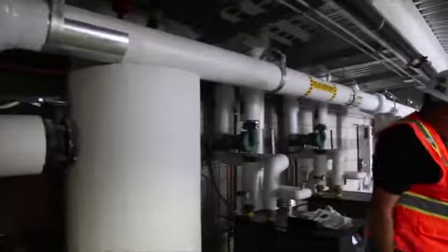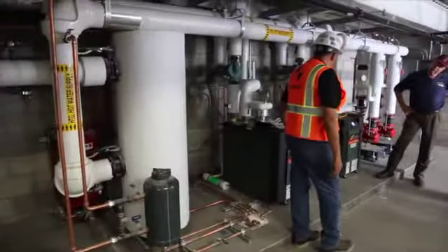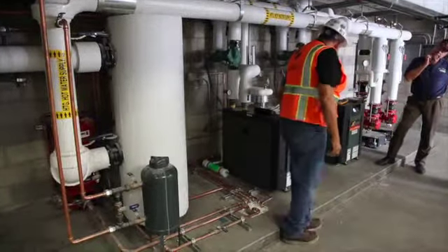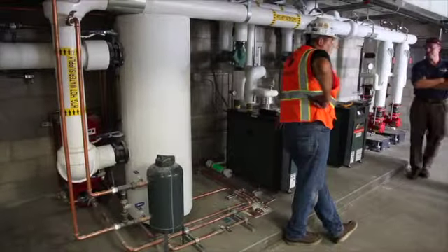So, what happens on the automation system, they enable a relay. It tells the lead boiler to start. You have a master and slave boiler. They use a communication cable between the two boilers. Right now we're having some difficulties with this particular boiler, boiler 1. We're going to get it addressed, but now we're on boiler number 2.